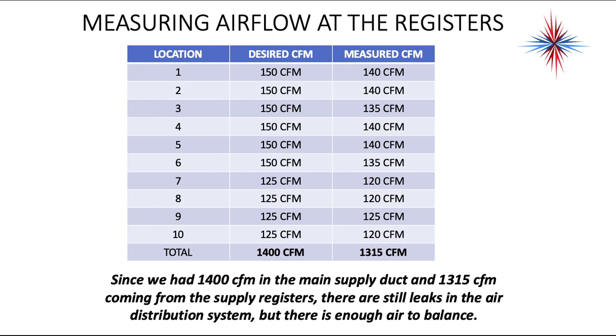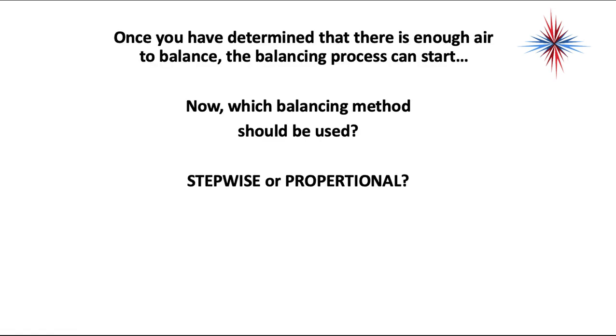After repair, we end up with 1,400 CFM in the main supply duct — measured coming out of the blower or air handler — and 1,315 CFM coming from the supply registers. There are still leaks in the air distribution system, but we're within 10%, so there's enough air to balance. Ideally I'd want that number to be closer, but we can proceed.